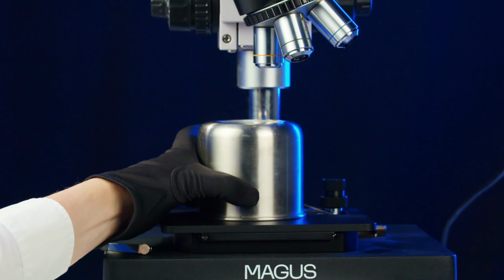Optical system. The objects studied with a metallographic microscope are opaque, so the device operates in reflected light. Light from the lamp passes through a system of lenses, is reflected by a mirror, and directed onto the sample through the objective, then returns back into the objective. The objective forms a magnified image and directs it to the eyepiece or to the camera. In a standard metallographic microscope, the objectives are located above the stage. The surface being examined must be perpendicular to the optical axis.